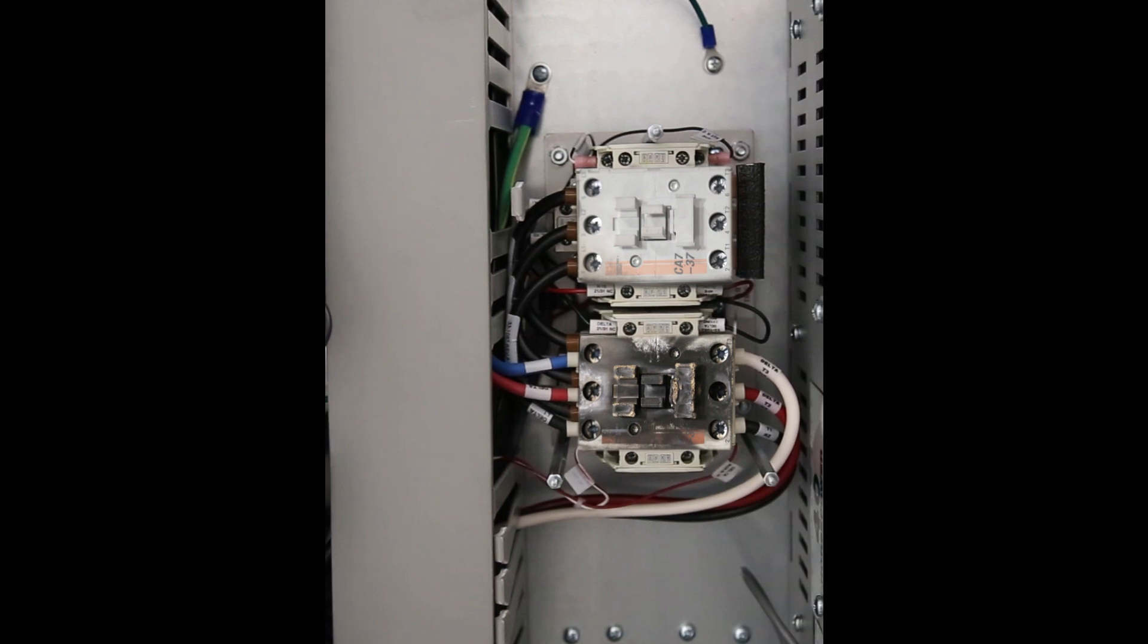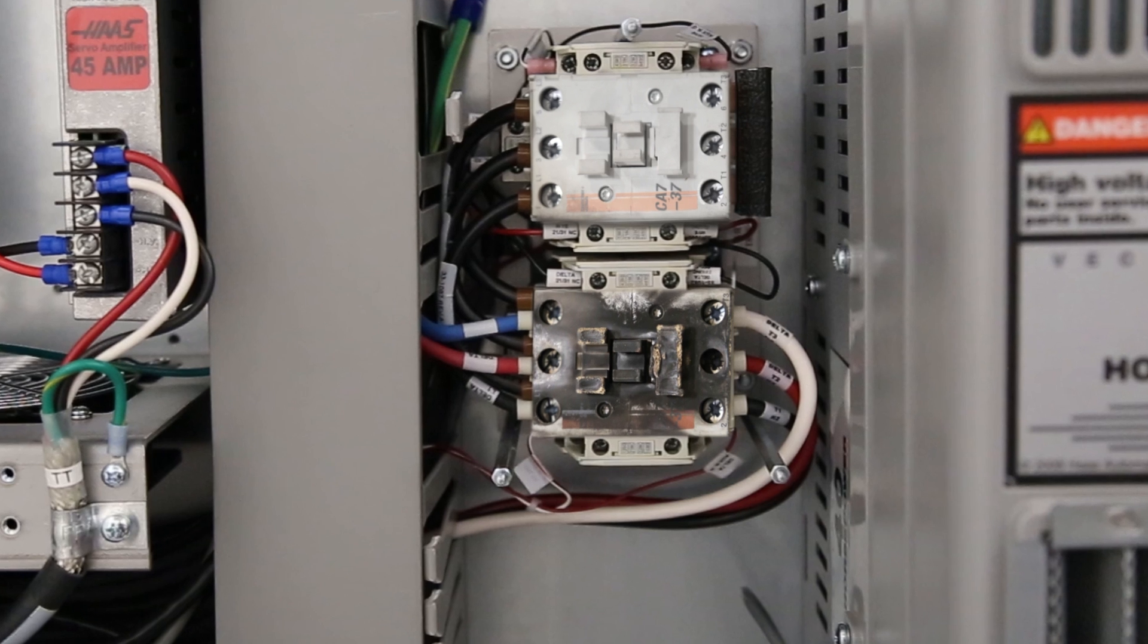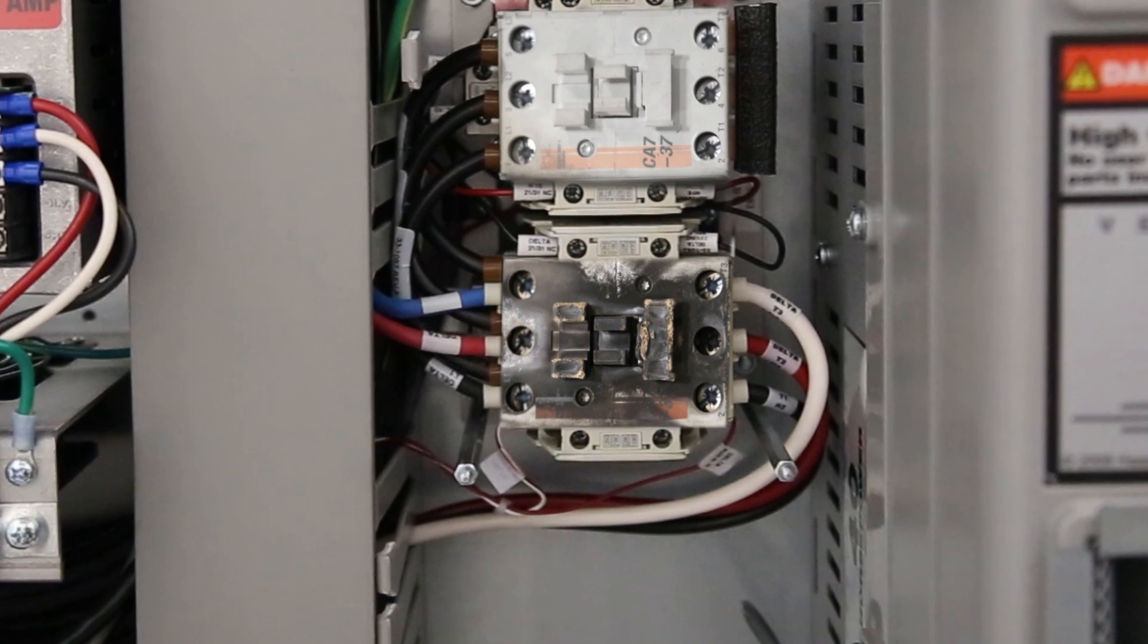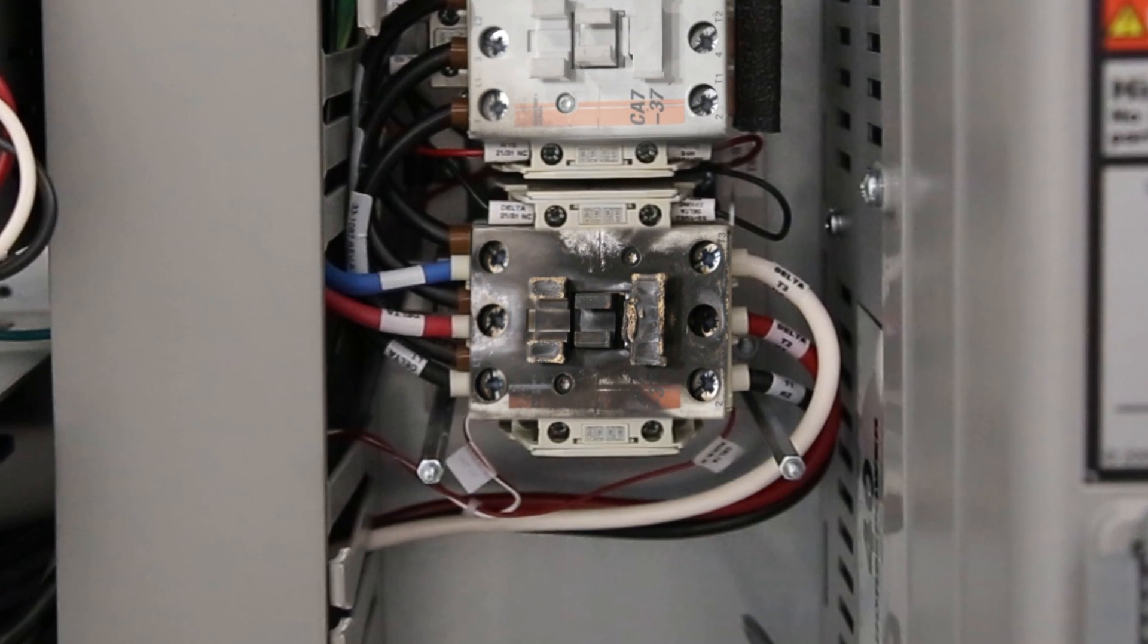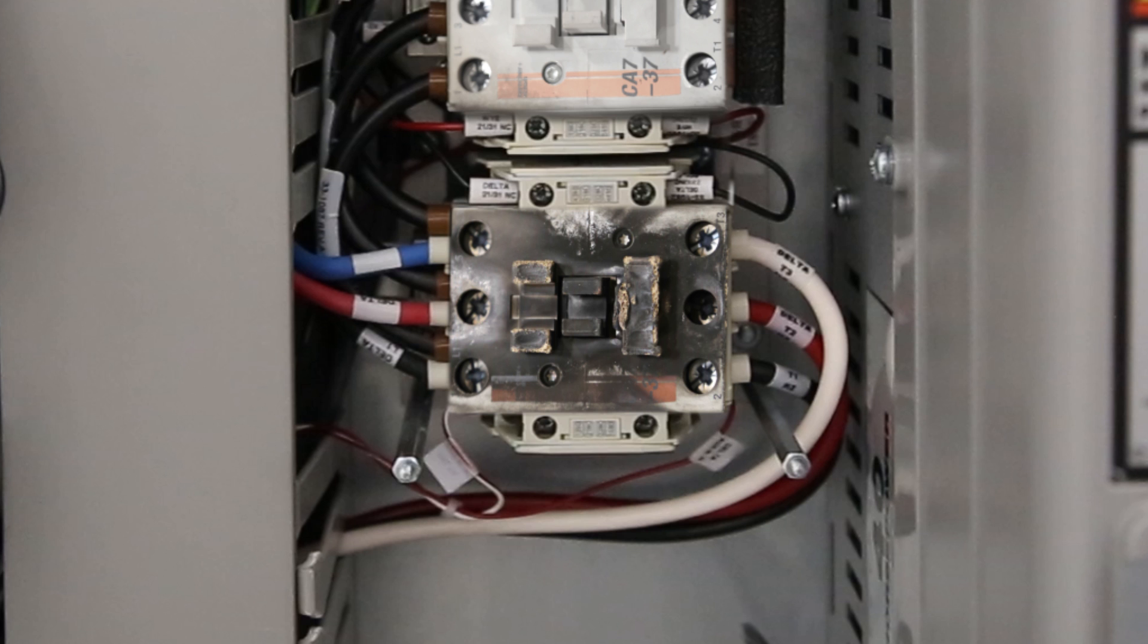If you've verified that your incoming power is stable and you're still getting persistent alarms, or you found damage to the Y-delta contactor, then it's time to contact your local HFO for assistance.